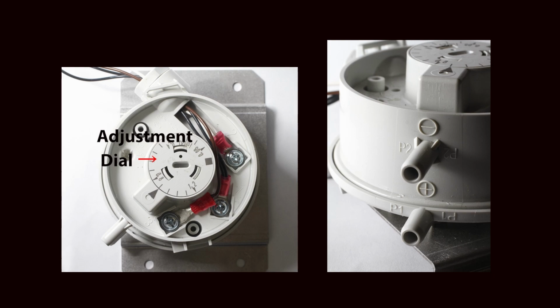They are a tool for tuning the burner. This factory setting on this dial can be adjusted to produce more or less air. Voltage measured at positions 1 and 3 when the fan is idle should be 9.3 volts DC, plus or minus 0.2 of a volt. Voltage measured at positions 1 and 2 with the fan running should be 24 volts DC plus or minus 1 volt. The pressure hose is always attached to the positive port. The negative port is a vent.